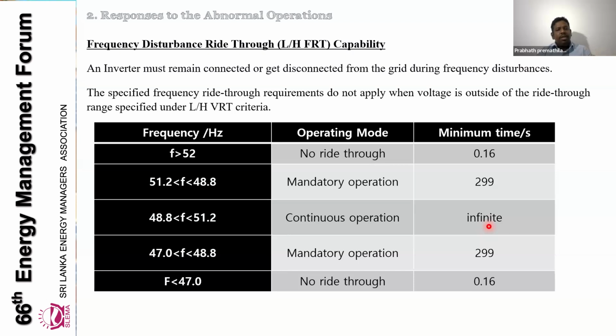Similarly, we can define 48.8 to 51.2 Hz as the normal operating range. We don't need frequency ride through there. But if the frequency is dropping below 48.8 and is between 47 Hz, the inverter should remain connected to the network and should support frequency ride through for up to 300 seconds. If the frequency is less than 47, there is no ride through requirement, but the inverter should stay connected for up to 160 milliseconds. If the frequency drops below 47 for more than 160 milliseconds, the inverter can trip and isolate from the network.